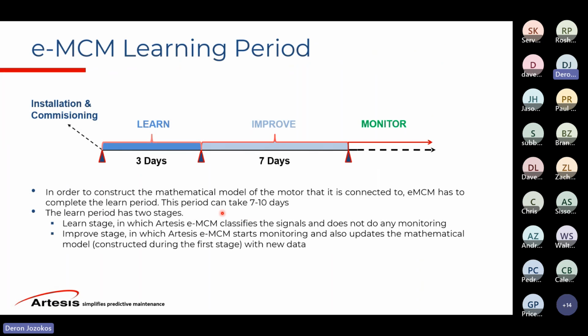So in recap, the learning period of how the system works is 3 to 4 days of the learn, where it finds all of your existing faults. For VFD systems, any variable speed systems, we shorten that to about 10 hours. And then the improved mode is 6 or 7 days to build those math models on fixed speed machines. But for the VFD, we want to learn more and extend that period, so we give it a full 10 days of math model building.